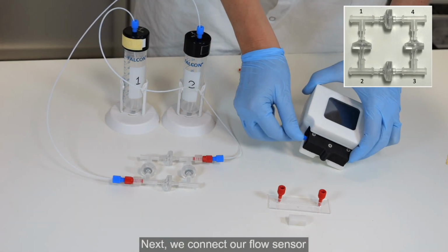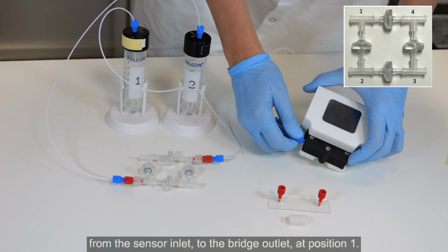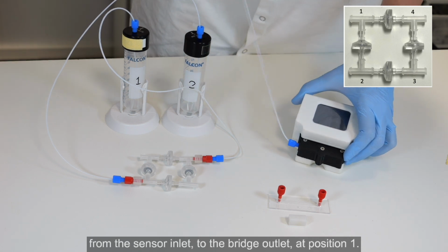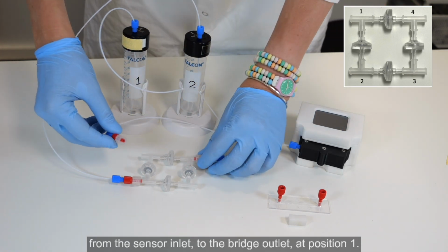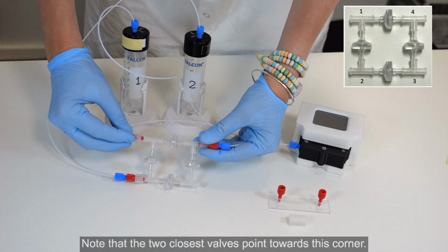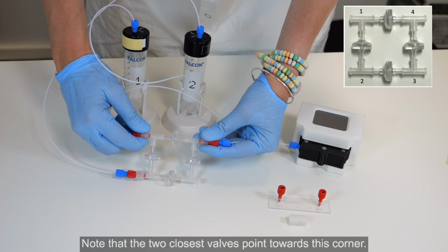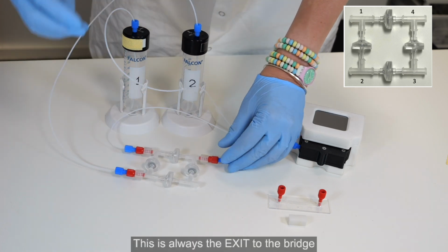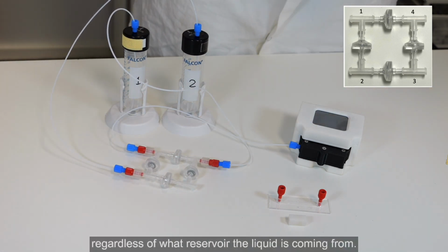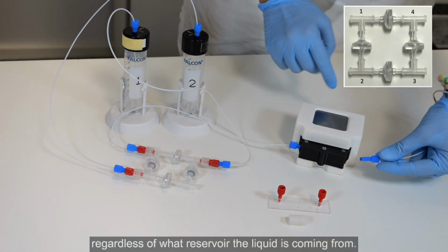Next, we connect our flow sensor from the sensor inlet to the bridge outlet at position 1. Note that the 2 closest valves point towards this corner. This is always the exit to the bridge, regardless of what reservoir the liquid is coming from.